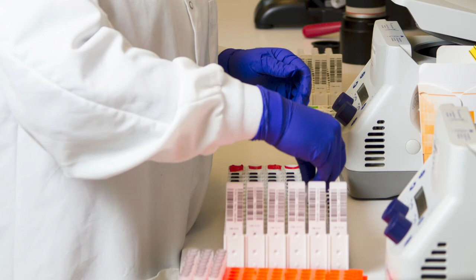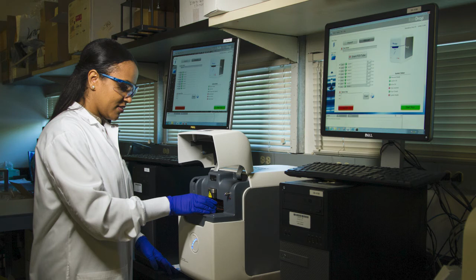Container incompatibility. Residuals in the container can react with the new chemical stored and degradation can occur. Do not add new reagent to the loaded reagent even if they have the same lot number. This will spoil all the reagents. The stability time can be decreased by the lab if required, but never extend the reagent stability time or QC runs, and never extend the calibration time.